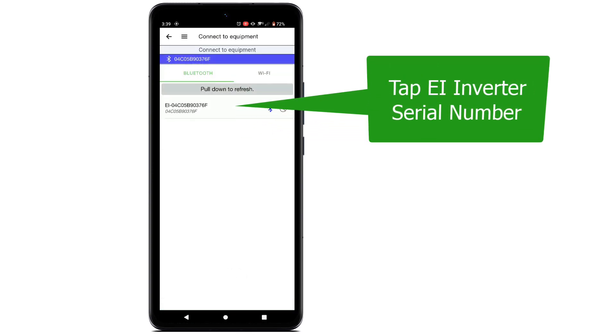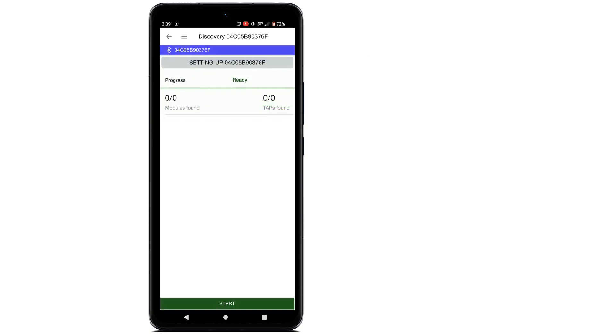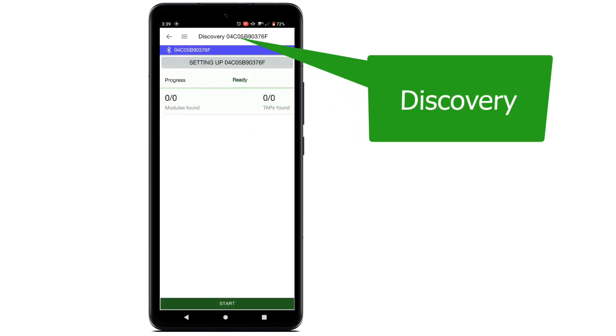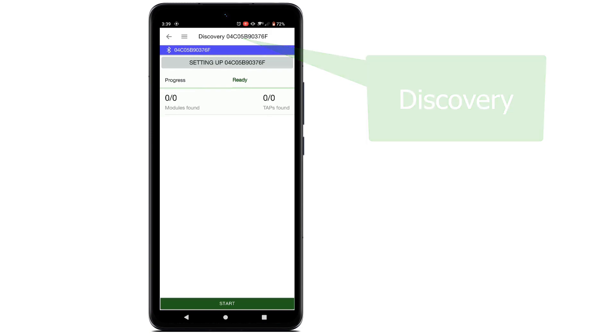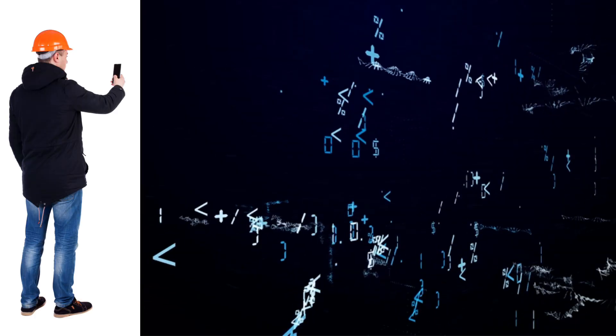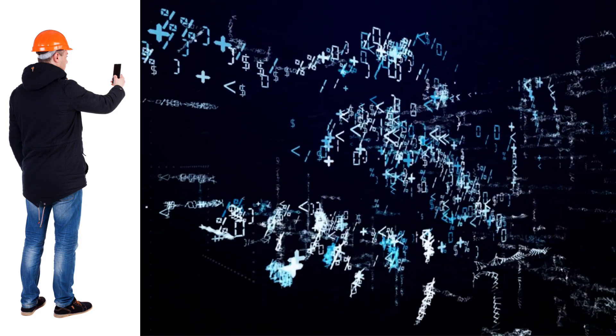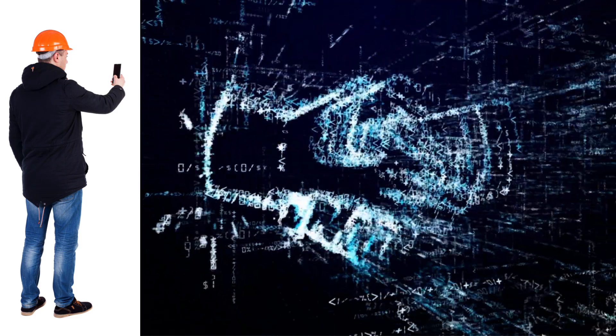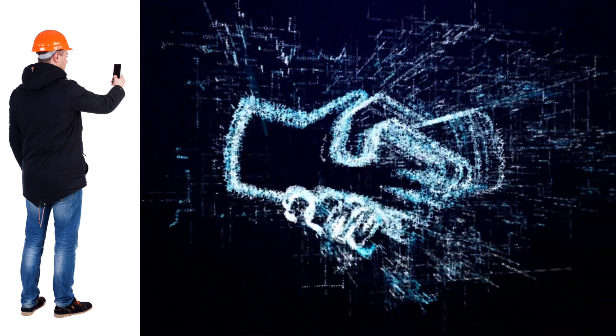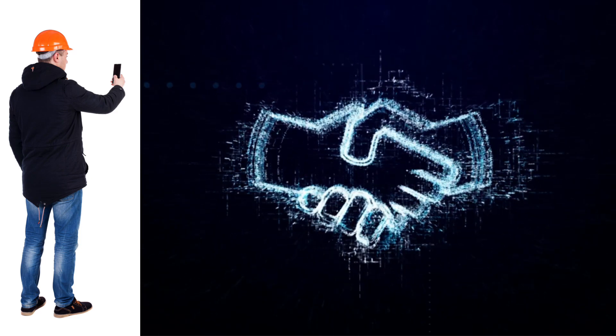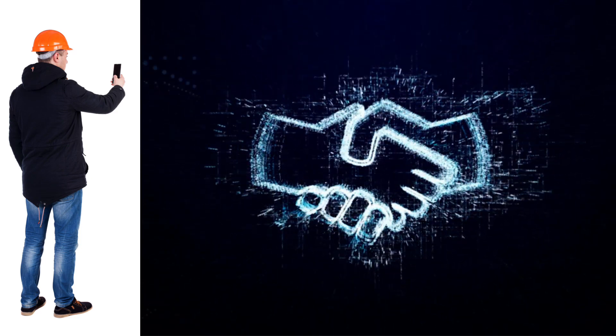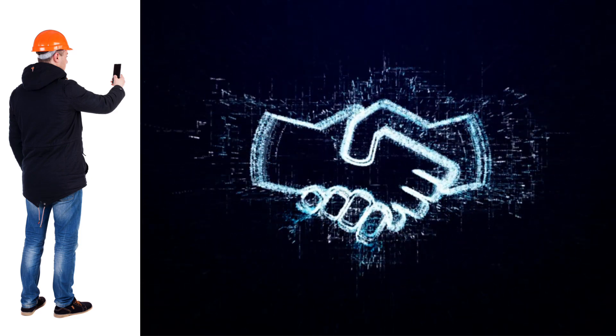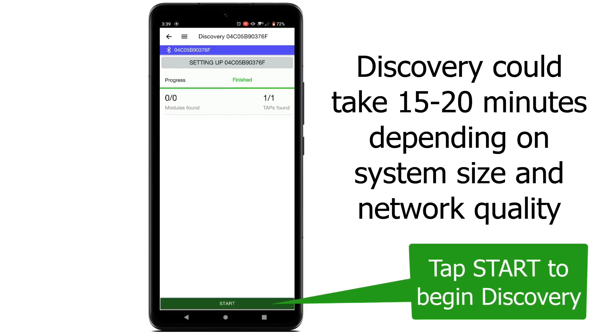Now we are in the final stages of commissioning. This last phase is called discovery and is identified at the top of the screen. During this phase, the CCA queries the Tigo server for the configuration file to begin the process of searching for each TS4 entered in the previous steps. This query and reception of the file can take some time, but is usually complete in a few minutes depending on network quality.